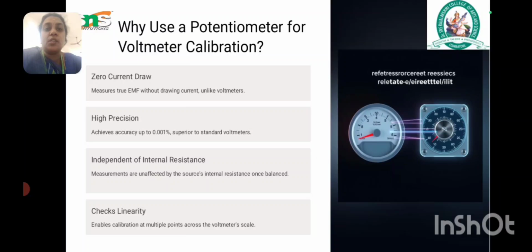High precision achieves accuracy up to 0.001 percent, superior to standard voltmeters. Third, independence of internal resistance: measurements are unaffected by the source's internal resistance once balanced. Then, check linearity: this enables calibration at multiple points across the voltmeter scale.